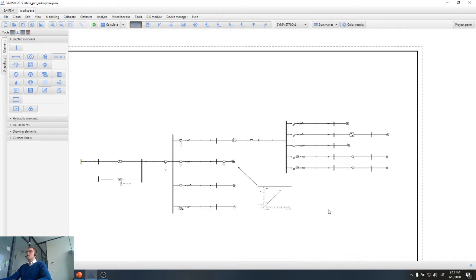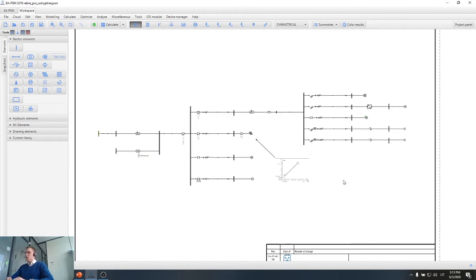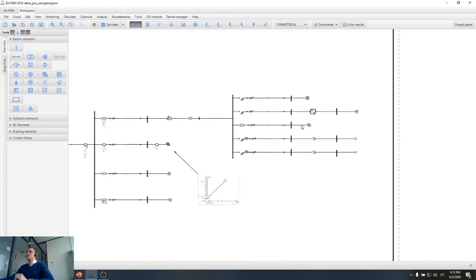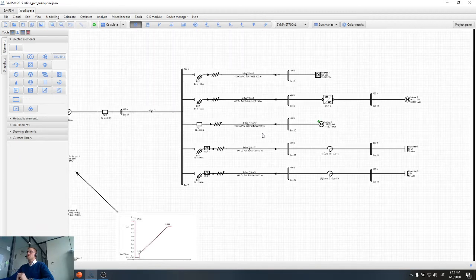So this is our network example, and today we will basically work on protection coordination in this electrical network. So let's start from the main principles of protection coordination, and I would distinguish three main principles. One of them is protection device sensitivity. Sensitivity means that if we have a short circuit, the protection device should be capable of sensing the short circuit current, and we have to select a protection device so that its setting current should be low enough to be capable of distinguishing the short circuit current.